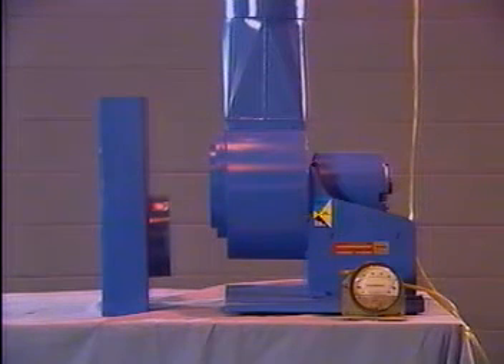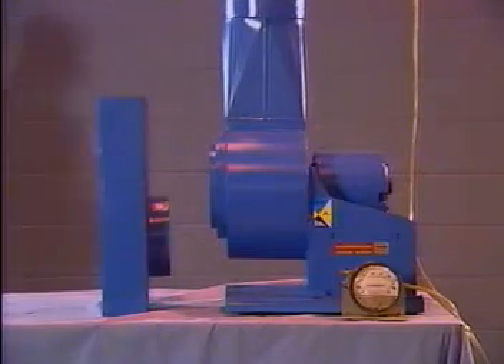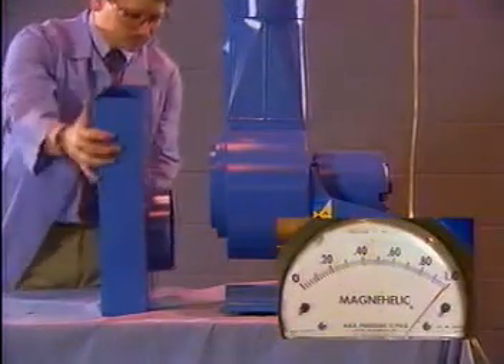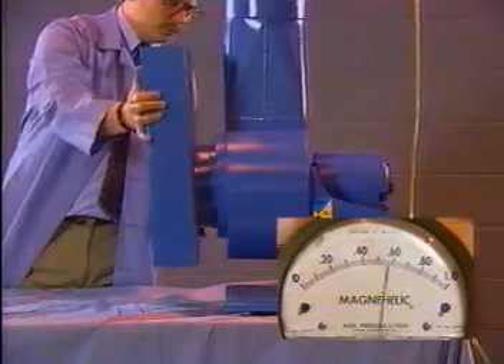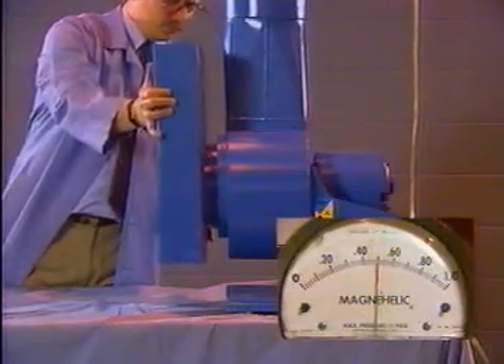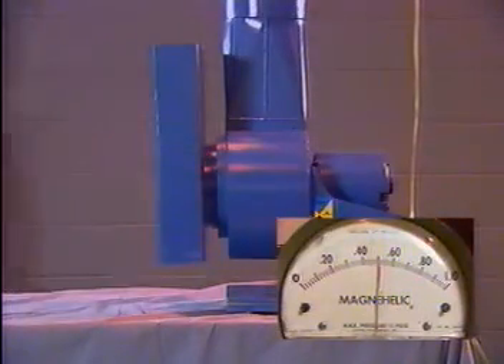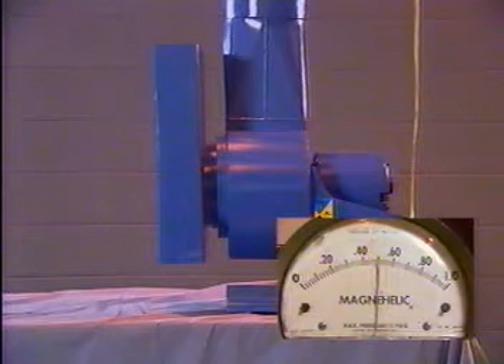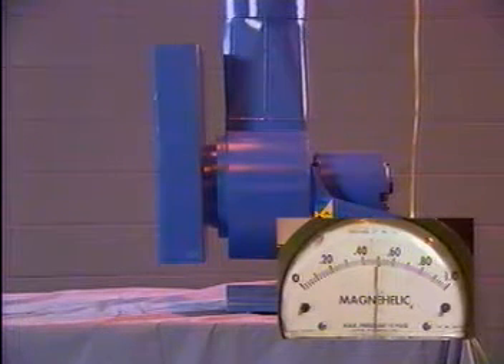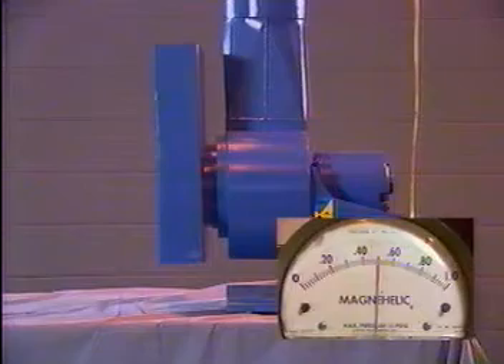Uneven eccentric airflow causes turbulence. Turbulence in turn reduces fan performance. We can simulate eccentric flow in the lab by attaching a poorly designed inlet box. The pulsation or surging sound you hear is caused by disrupted airflow. That means the fan is not performing at peak efficiency.